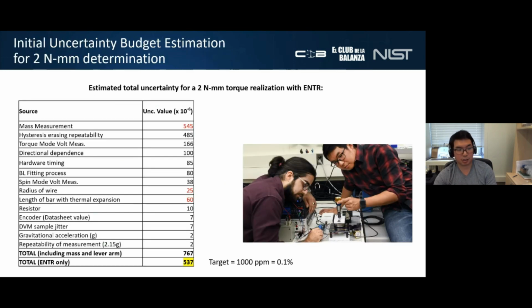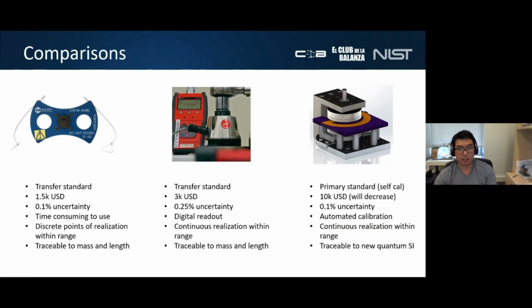Here's our preliminary uncertainty budget. Our target is 0.1% or 1,000 ppm. And even when we fold in the uncertainty of the mass and lever arm, which are the terms in red, which we use as a verification technique for checking our ENTR performance, we're still within the specs. And this was determined at 2 newton millimeters. Here's a comparison between two industry transfer standards against our primary standard. So ENTR demonstrates that direct torque realization is possible, and at 0.1% is not very difficult to achieve, especially when it comes to truncating this, in my opinion, very wasteful and long traceability chain.